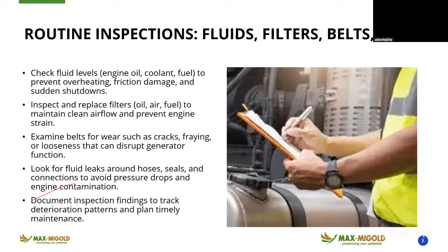So pay attention to details. Carrying out routine inspection with a checklist on a daily basis, weekly basis, as the case may be, helps to prolong the lifespan of your generator. Inspect and replace filters, oil, air, fuel, to maintain clean airflow and prevent engine strain. If they are not replaced when they are meant to be, it forces the engine to overwork, other components might get damaged and stressed, and in the long run you end up spending money that you are not meant to spend because you did not do what you were meant to.